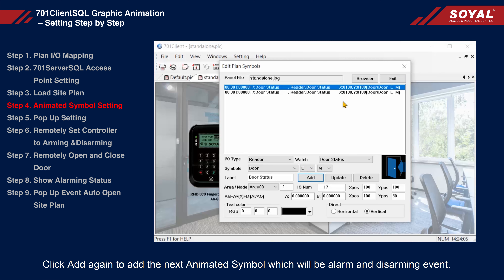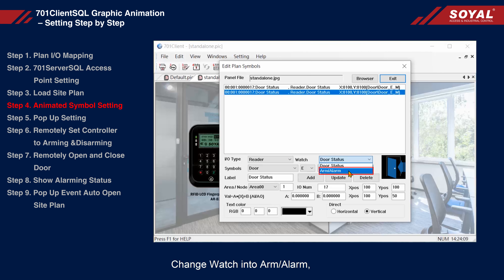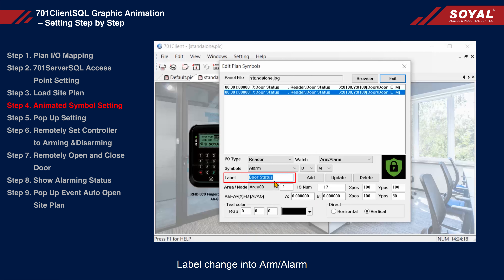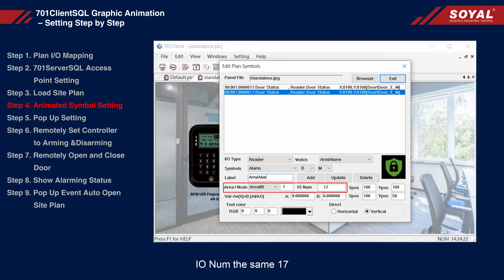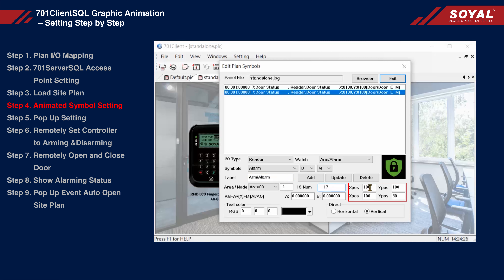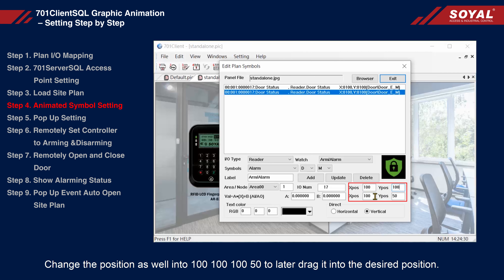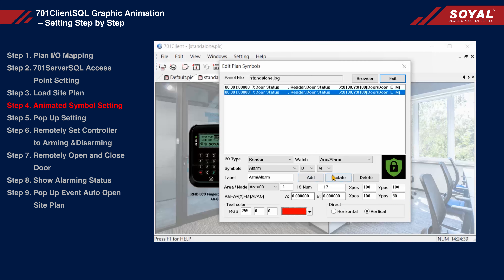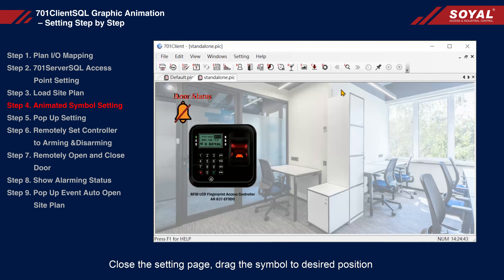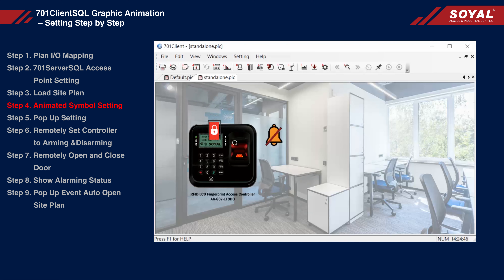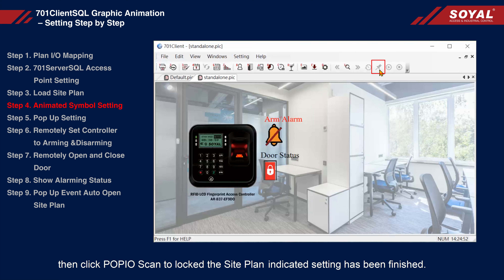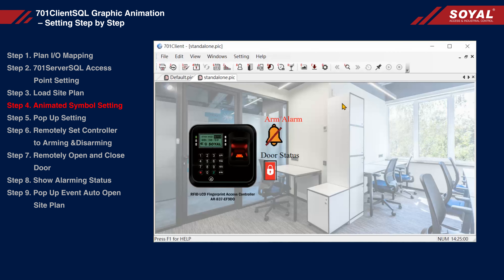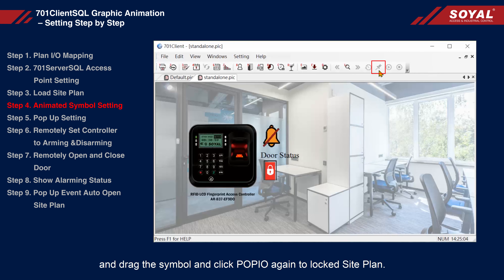Click Add again to add the next animated symbol, which will be the arm/alarm event. Change the Watch to arm/alarm, symbol select Alarm, and change the type to D. Change the label to 'arm/alarm'. The I/O number will be the same, which is 17. Change the position to 100, 100, 150, to later drag it into the desired position. You can also change the text color to red, for example. Then click Update to save changes, close the setting page, drag the symbol to the desired position, and then click Pop IO Scan to lock the site plan, indicating the setting has been finished. To edit again, select Edit > Graphic Contents, close the window, drag the symbol to the desired position, and click Pop IO again to lock the site plan.